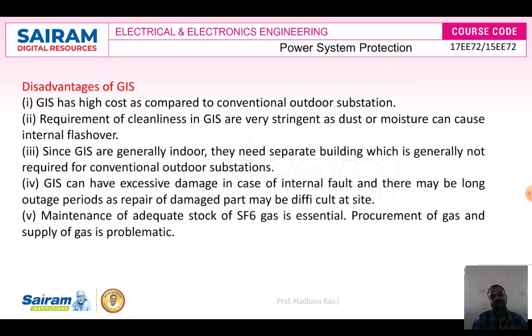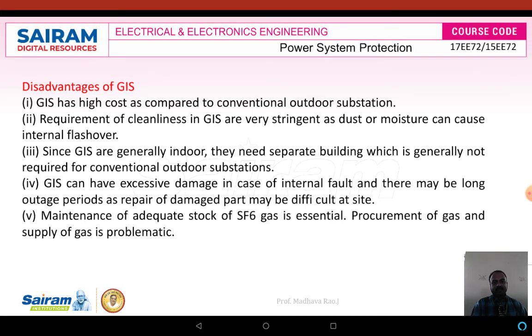This is to avoid dust and moisture. GIS can also have excessive damage in case of an internal fault. And next, maintenance of an adequate stock of SF6 gas is essential. Once the SF6 gas is over, the equipment will not work, right? That is why an adequate stock is required, and procurement and supply of the gas is problematic. It is very dangerous, so we have to transport it safely from that place to our substation. That is one major disadvantage in GIS.